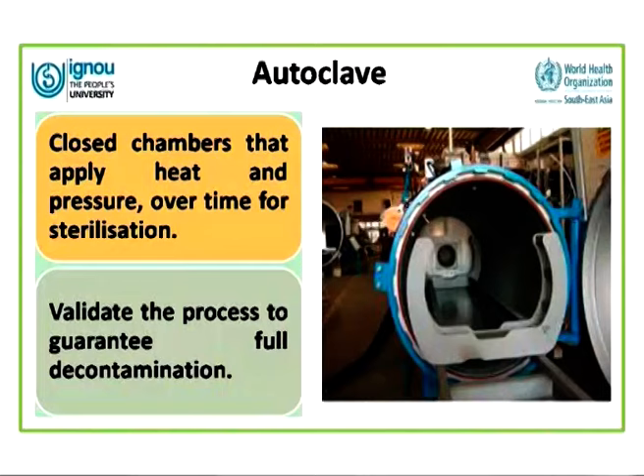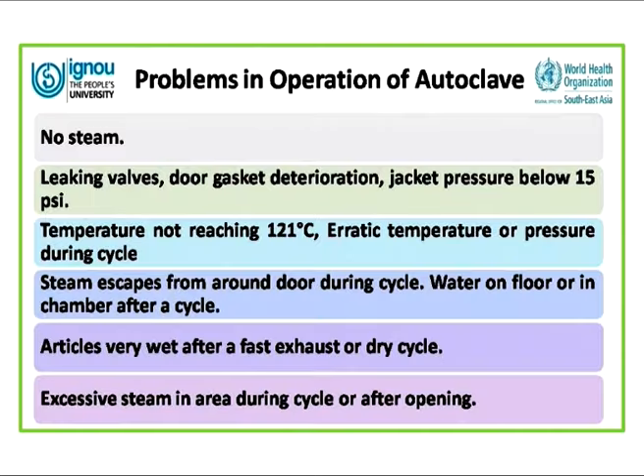Let us learn more about these different types of processes because they are very commonly used and in many places replacing the incinerators. So we have got the autoclave. You can see the picture of an autoclave here. It is a closed chamber that supplies heat and pressure over time for sterilization, and they validate the process to guarantee full decontamination. But there are certain problems that may crop up in an autoclave and you must know what problems you may encounter while operating one.